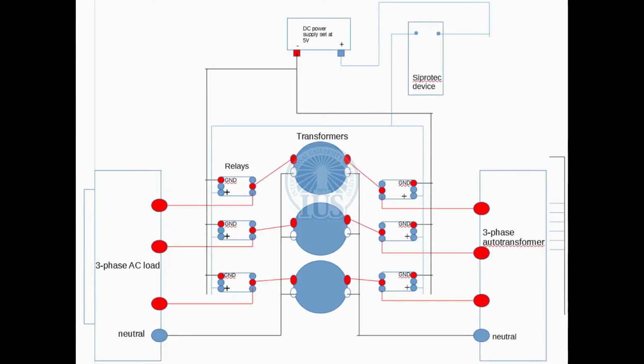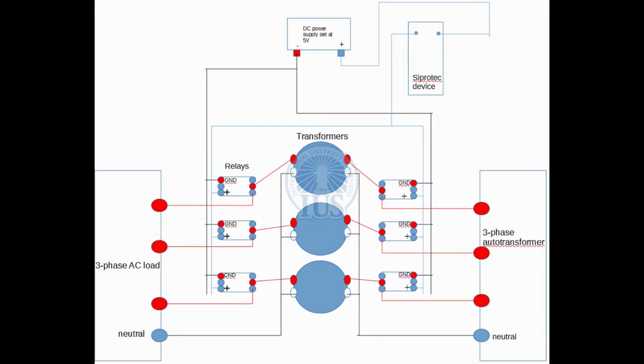On the protection side, as you can see, we have 3 single-phase transformers connected Y to Y. They make a single 3-phase transformer. Because we have 3 phases on both sides, we need to break all 3 phases with a circuit breaker. That's why we need 6 single-phase or 2 3-phase circuit breakers. In our case, again, we use relays for that. In real world applications, we couldn't use relays because the currents are too high and the relays cannot trip such high currents. They would break, burn, or whatever. But in our case, it worked.